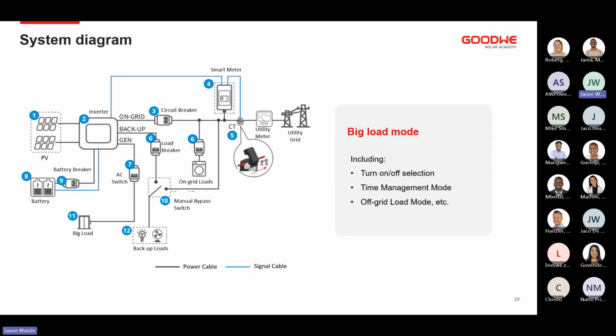So you can set when you want to run them at a high level of battery SoC, and when it reaches a set limit that you've input, you'll be able to disable that port and allow your other loads to continue for longer until, obviously, you get your grid or PV back up so that you can charge your batteries higher up again.